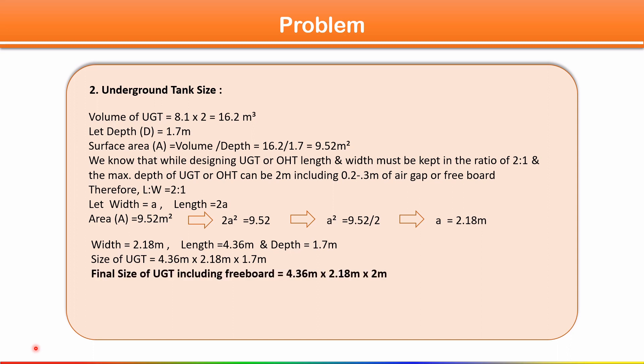Including freeboard of 0.3 meters, the final size of underground tank is: length = 4.36 m, width = 2.18 m, total depth = 2.0 m. This is how we find the capacity and size of both the overhead tank and underground tank. I hope you enjoyed the session — see you in the next one.